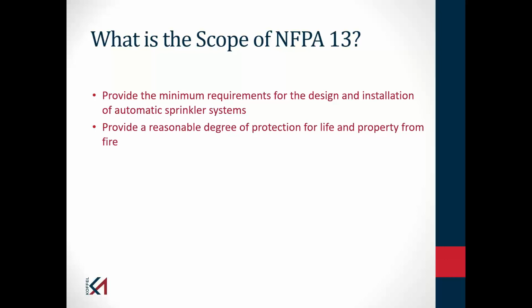And I just want to focus on that for a moment, because many people look at sprinkler systems as a property protection feature in the building. And that comes from the old insurance perspective and the buildings that we used to install sprinkler systems in: the industrial occupancies, the highly protected risks, the warehouses, storage occupancies, and so forth. But today, as required by most building codes, you are probably putting sprinkler systems in almost, if not every building that you build and or rehab on your campus. And that is in part due to the fact that there has been identified, with some changes in sprinkler technology, a life safety benefit to installing sprinkler systems.